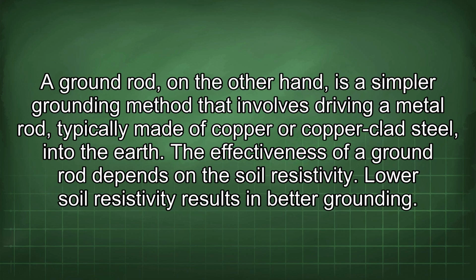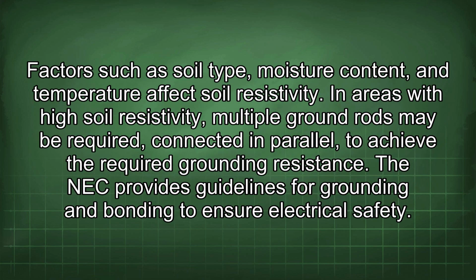A ground rod, on the other hand, is a simpler grounding method that involves driving a metal rod, typically made of copper or copper-clad steel, into the earth. The effectiveness of a ground rod depends on the soil resistivity. Lower soil resistivity results in better grounding. Factors such as soil type, moisture content, and temperature affect soil resistivity. In areas with high soil resistivity, multiple ground rods may be required, connected in parallel to achieve the required grounding resistance.